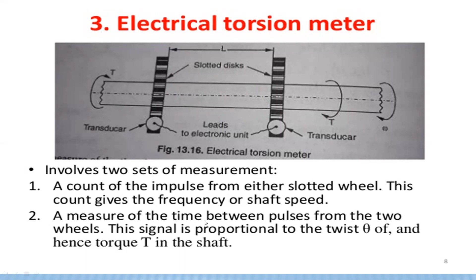There is a twisting moment that occurs. So this twisting moment is calculated by measuring the time between the pulses from the two wheels by using these transducers. Okay, so it involves two sets of measurements: a count of impulses from either slotted wheel, and it measures the time between pulses of the two wheels. These are the two main things in the electrical torsion meter.